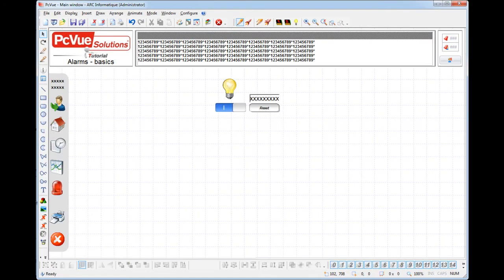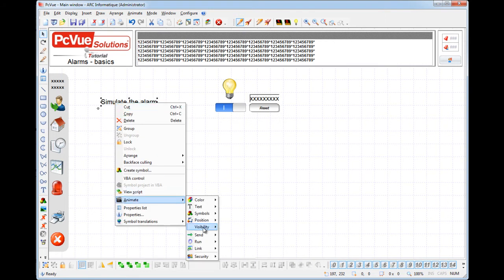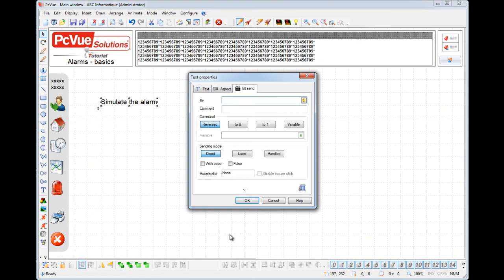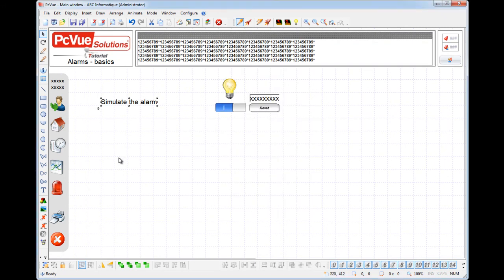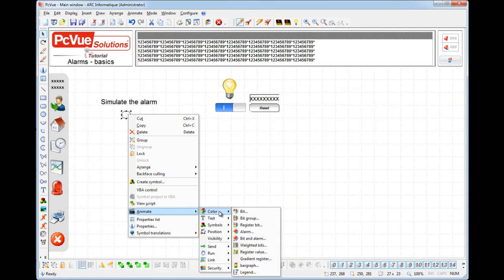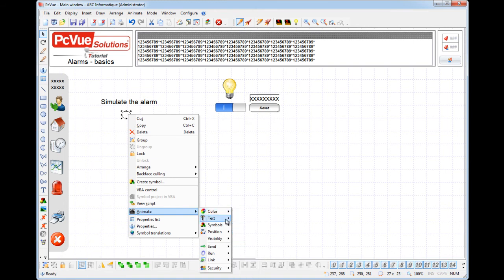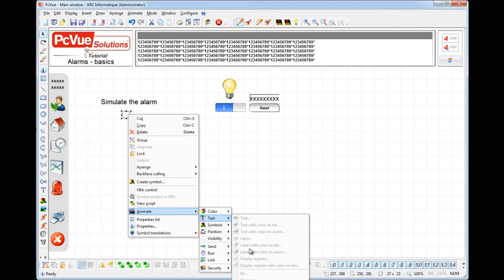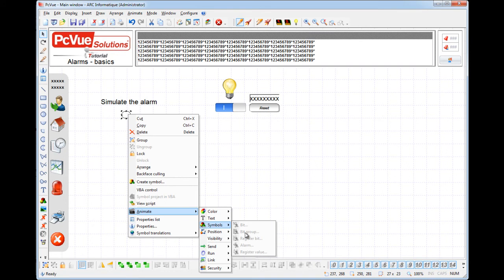First, we'll create a new text to simulate the alarm. Since an alarm variable is a variation of a bit variable, if its command property is set, you can control its value using a send bit animation. Select the alarm 'general alarm'. Now let's create an object to display the status of the alarm. Depending on the status of the alarm, you are able to change the color of an object, display a specific text. Animations are disabled here as we don't use a text object. Display a symbol, and hide or show an object.